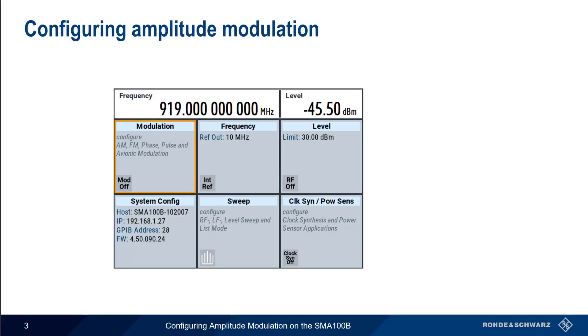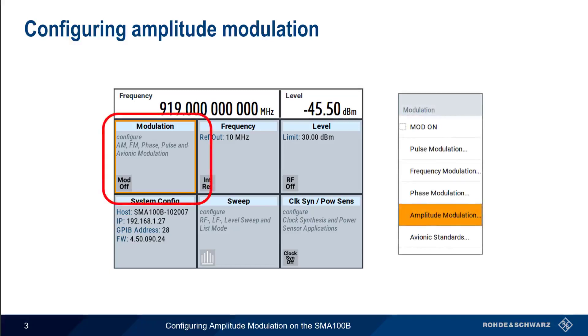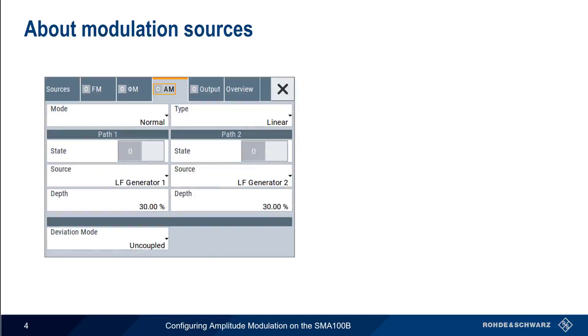To enable analog modulation on the SMA100B, we simply click on the Modulation tile and then select Amplitude Modulation from the menu. Remember that modulation means varying some parameter of the transmitted carrier, so our first step is defining the modulating signal.